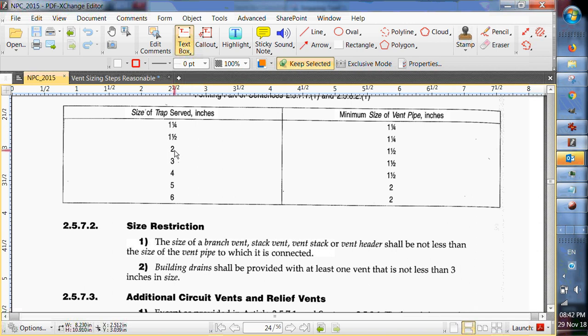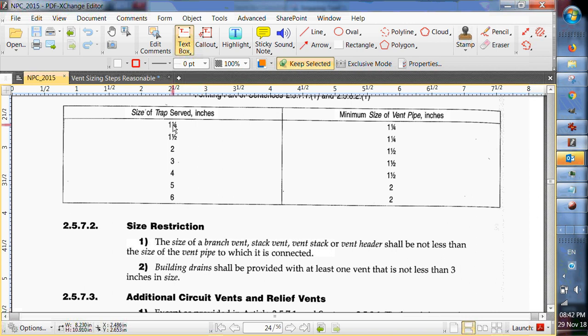Two inch for urinals, going to have an inch and a half vent. One and a quarter for one and a quarter pipe. So that's lavatories there. So let's go set those.